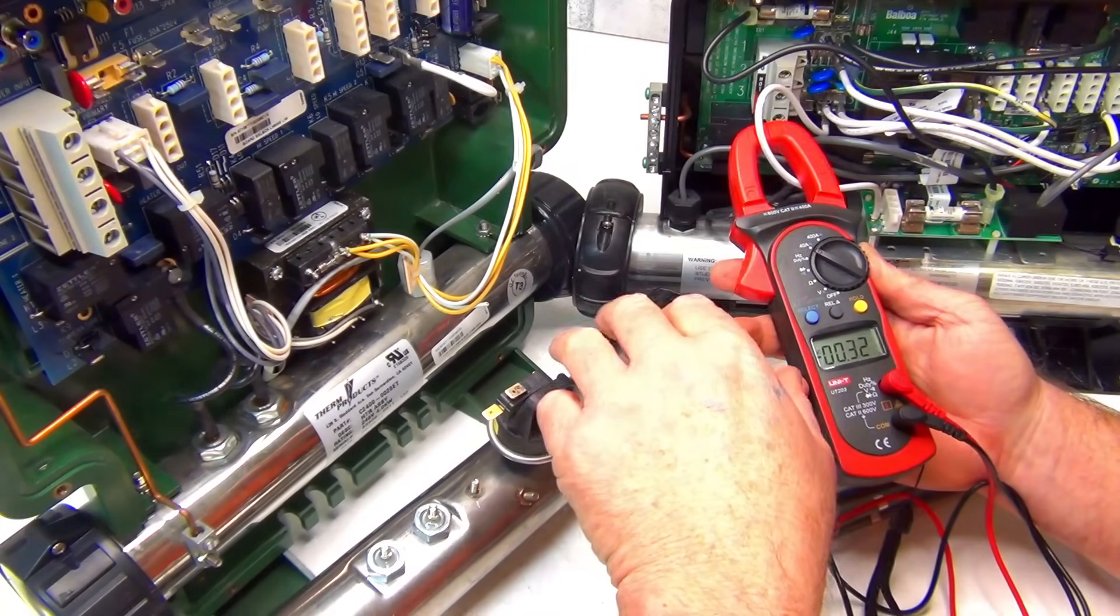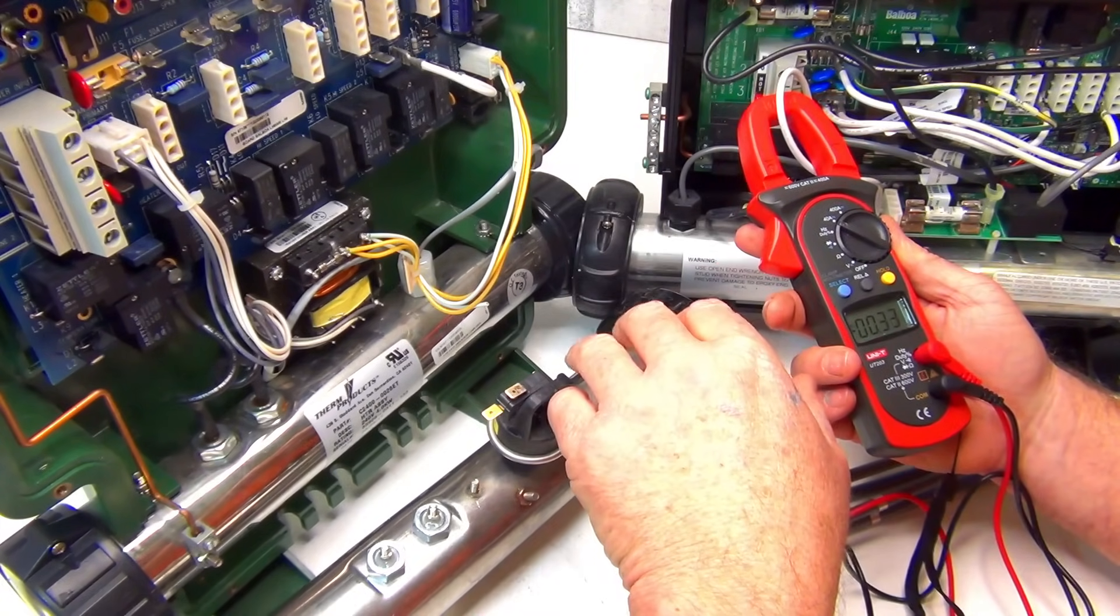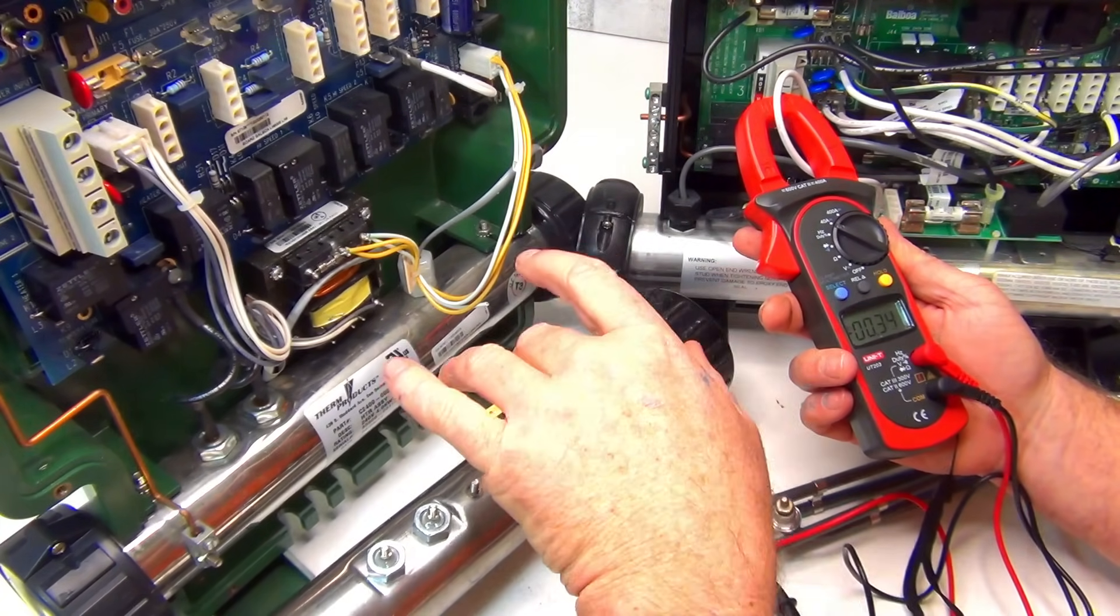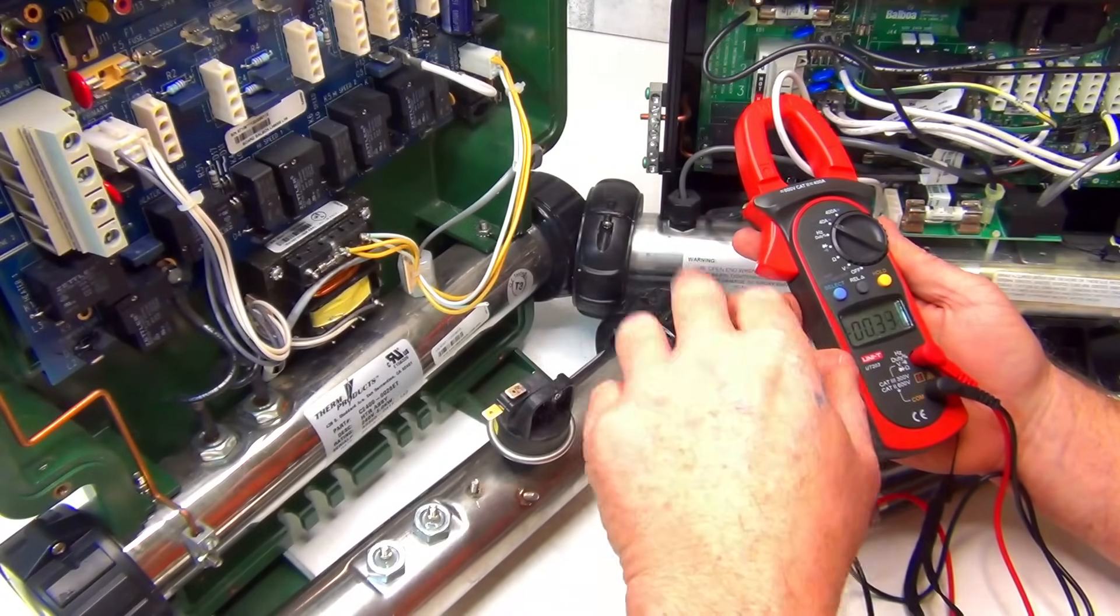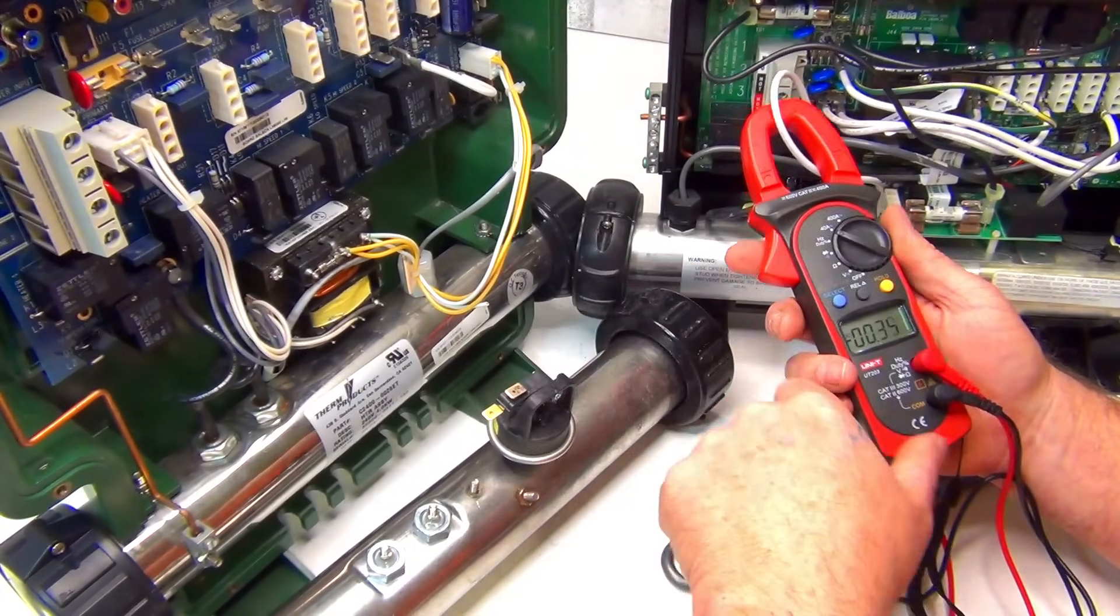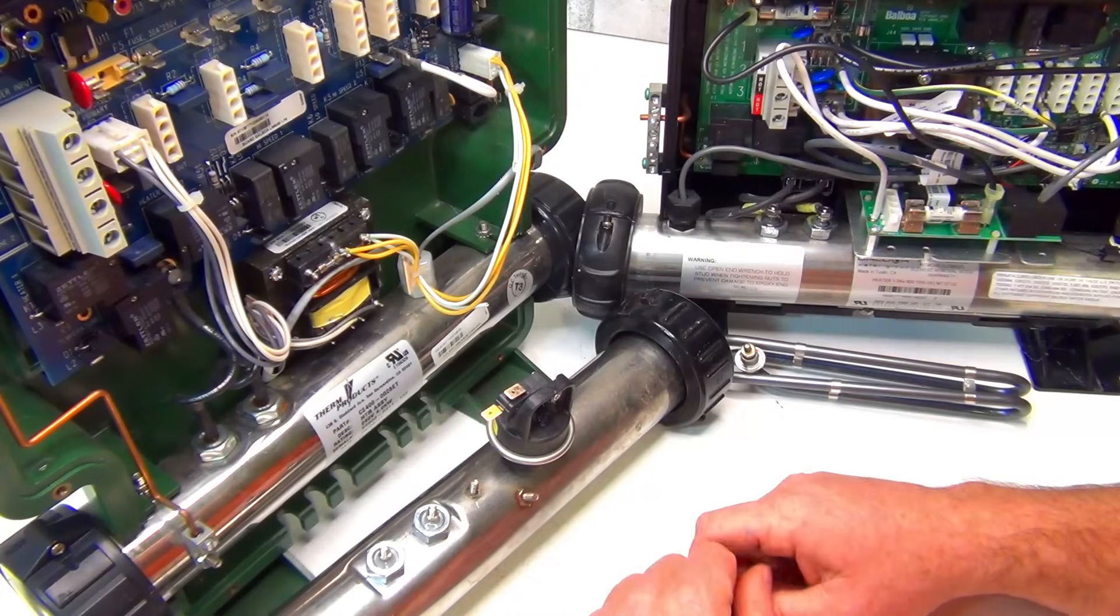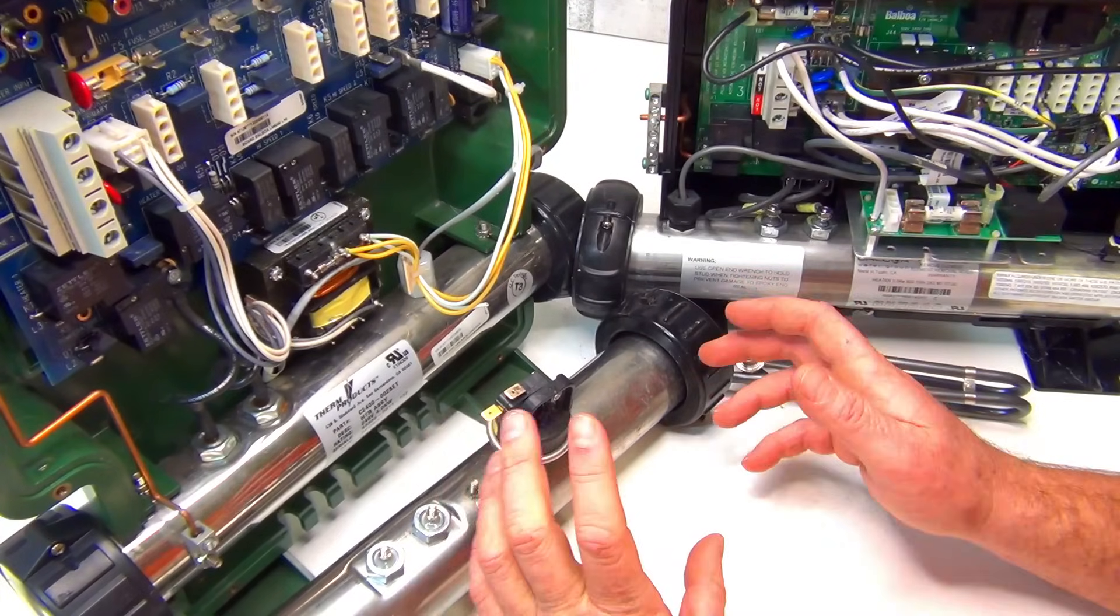And it'll give you an idea. Even if you put it on there and you put high speed, high speed, low speed is going to be different amperage. So you can check that on your hot tub pump. So there's the four ways of testing your heater element.